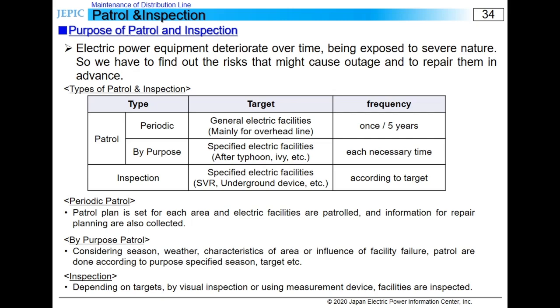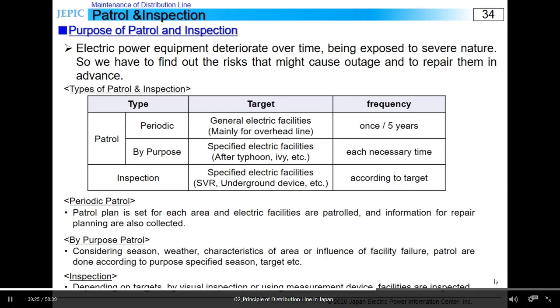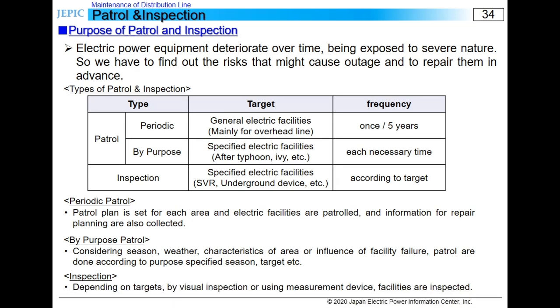Inspection targets specified electric facilities like SVR, underground devices, etc. in a certain period. Depending on the target, facilities are inspected closely, not only visually but also using measurement devices. The information acquired through patrols and inspections is accumulated and used for formulating a repair plan. Patrols and inspections are the basis of maintenance. Improvement of efficiency by using digital technologies is a key issue at the moment.